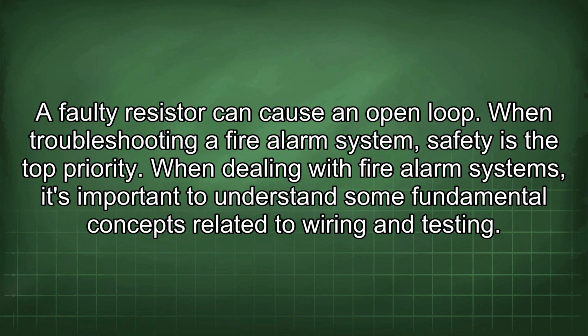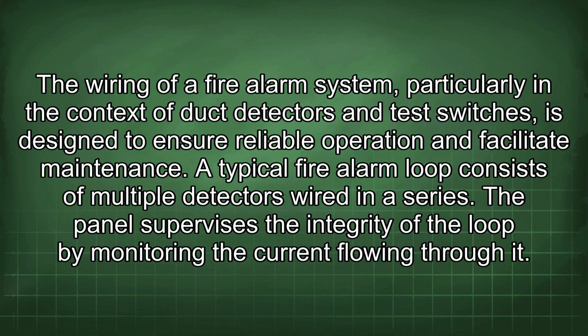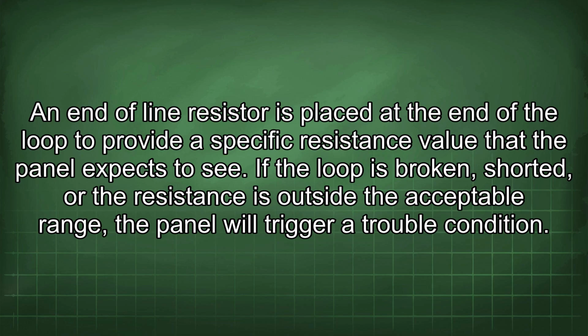When dealing with fire alarm systems, it's important to understand some fundamental concepts related to wiring and testing. The wiring of a fire alarm system, particularly in the context of duct detectors and test switches, is designed to ensure reliable operation and facilitate maintenance. A typical fire alarm loop consists of multiple detectors wired in series. The panel supervises the integrity of the loop by monitoring the current flowing through it. An end-of-line resistor is placed at the end of the loop to provide a specific resistance value that the panel expects to see. If the loop is broken, shorted, or the resistance is outside the acceptable range, the panel will trigger a trouble condition.